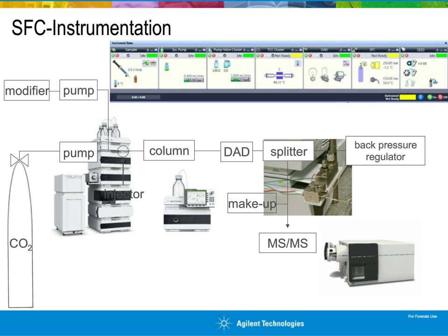What you see on top in that little graph there is the instrument control. This is MassHunter, as this is running on a triple quad instrument, and you can see basically every single module that you see in any of those stacks being represented here, which means in day-to-day routine operation, this is very easy going.